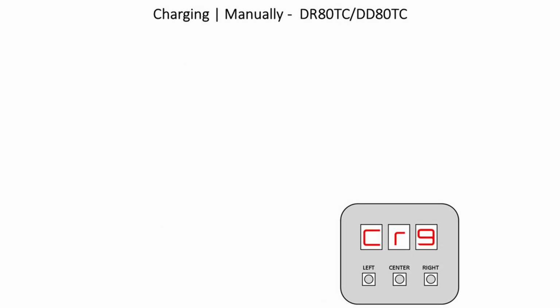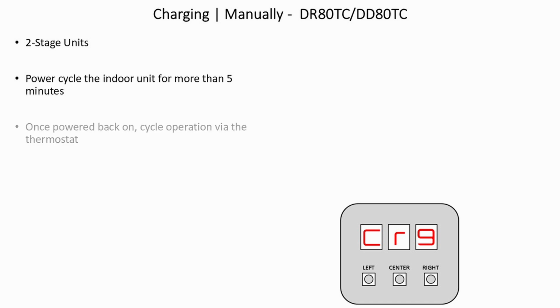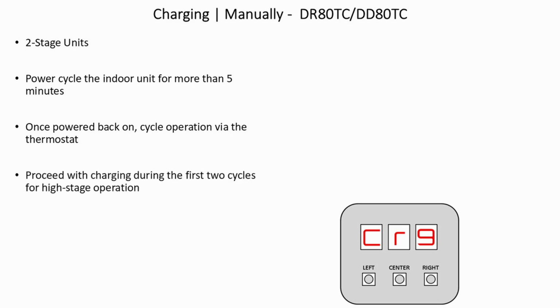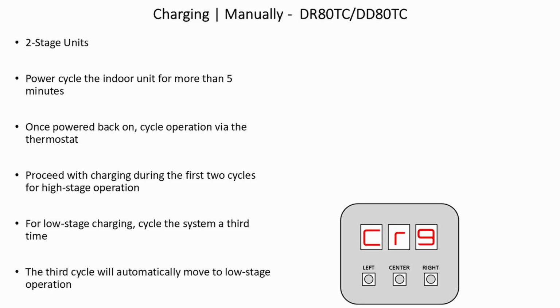Charging manually. For two-stage units, power cycle the indoor unit for more than 5 minutes. Once powered back on, cycle the operation from the thermostat. Proceed with charging during the first 2 cycles for high-stage operation. For low-stage charging, cycle the system a 3rd time. The 3rd cycle will automatically move to low-stage operation.